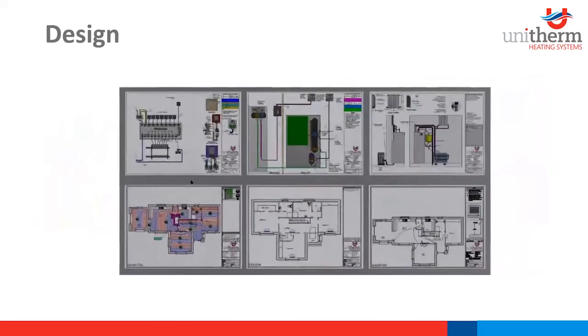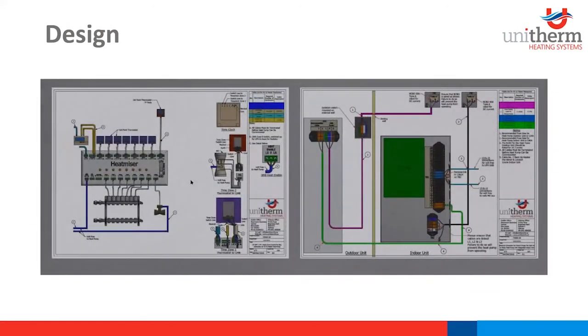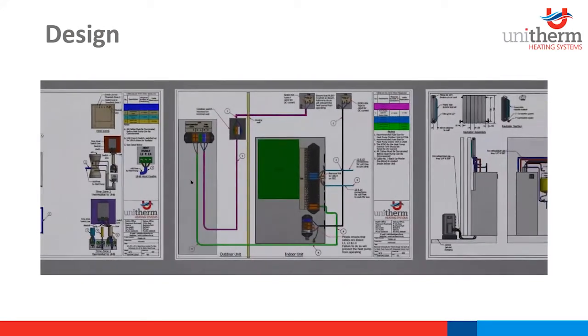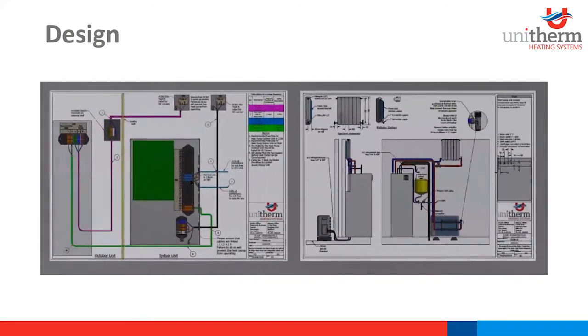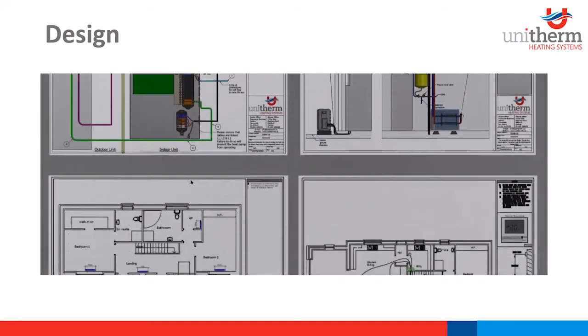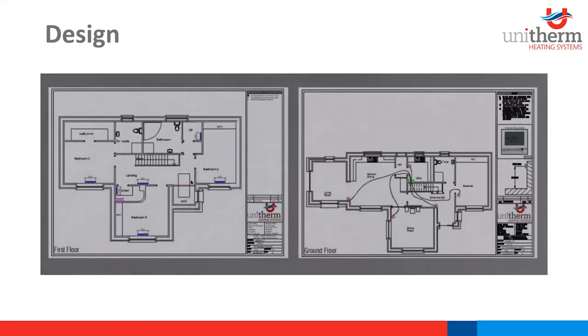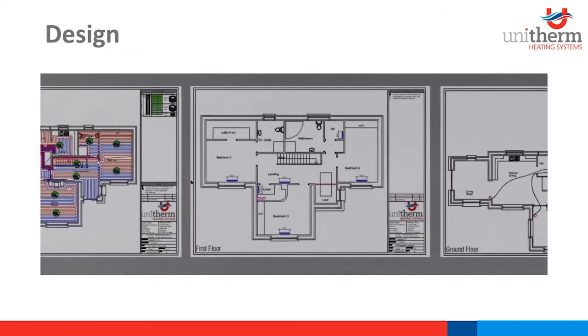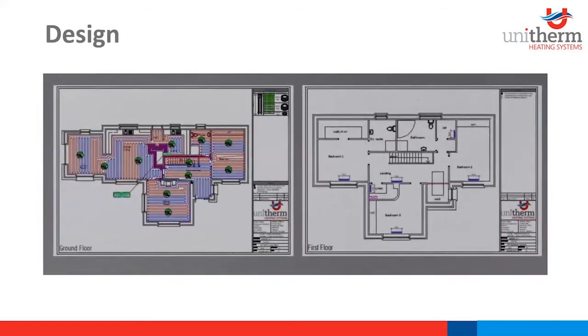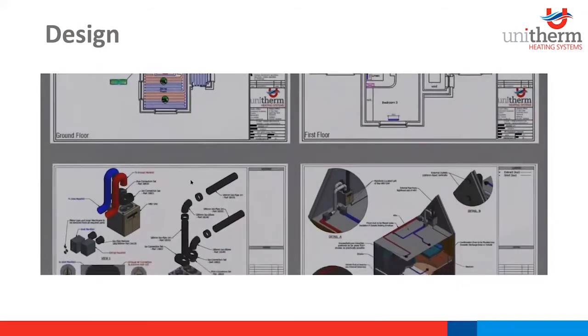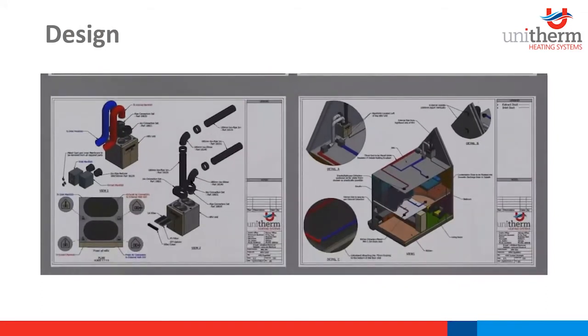So here are just some of the technical drawings that we supply. We say controls drawings there for stats, motorized valves, underfloor heating, actuators. There's a second fix schematic. So we do first fix electrical, second fix electrical, mechanical schematics for every project individually. There's thermostat layouts for the electrician, manifold layouts, radiator layouts, steel or aluminium, and then underfloor heating loop plans. So ground floor, first floor, second floor, whatever is required, and they come with heat loss calcs on them as well.